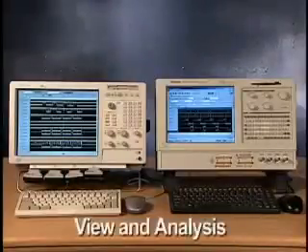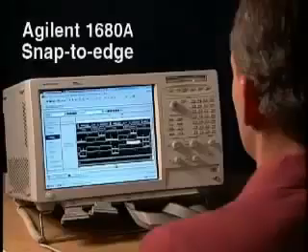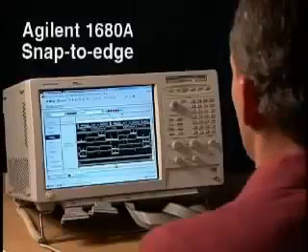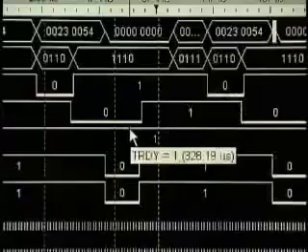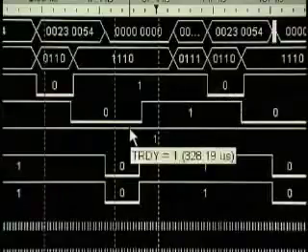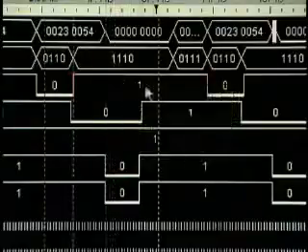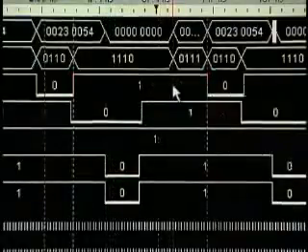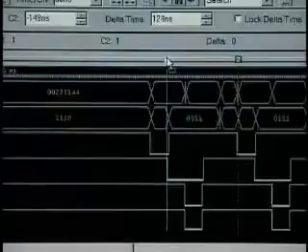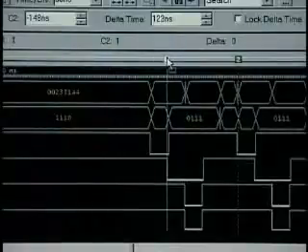When it comes to viewing and analysis of your measurement, Agilent's advantages continue with quick and accurate marker placement. For instance, here, Agilent's exclusive snap-to-edge feature makes placement of a marker on this falling edge literally a snap. This reduces the time and uncertainty of having to rely on manual marker placement required by the other logic analyzer.